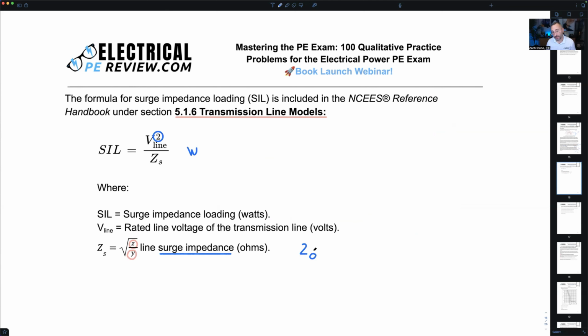also does what? It eliminates something called reflected standing waves on the transmission line. Another good qualitative topic. Same value. When we're talking about reflected standing waves, we describe this value as the characteristic impedance, ZO. When we're talking about reactive power consumed by the transmission line, and if it's being supplied by the transmission line, or if the transmission line's not supplying enough and some of it's being sent from the sending side, or if the transmission line is supplying too much and we have an excess amount being supplied to the receiving side, then we call this the surge impedance. But it's the same value, same formula.